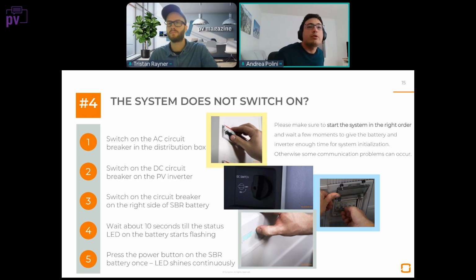You can do both of them in different orders, and in that case you must then see that the inverter switches on, the LEDs are on, and the inverter should recognize the battery. So you must wait a few minutes and check the detailed information of the inverter on the iSolarCloud web portal or in the local connection mode between your smartphone and the inverter. You should see the details of the battery appearing in the Run Information tab. The battery should be connected and recognized automatically. If the battery is not recognized, then we go back to the first point that we discussed today, which is that maybe the communication connection between the inverter and battery is not right.